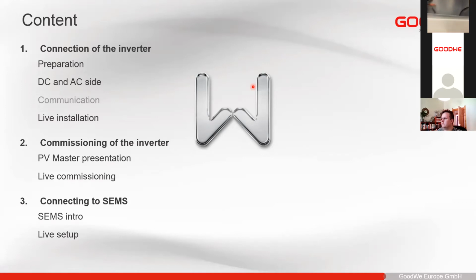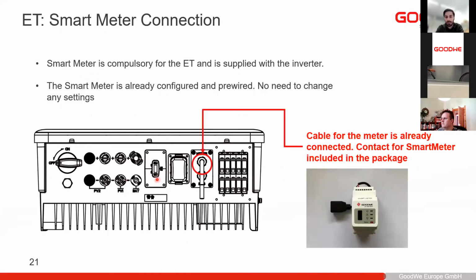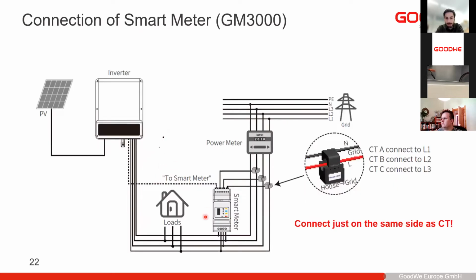And this is done via our app. Here, I see that the slide stopped now. Here is how you connect the smart meter. As you see here, this is how it should be connected. So the CTs are connected just before the meters, and the voltage stands as close to them as possible with all the load on the other side. So no load in between here.